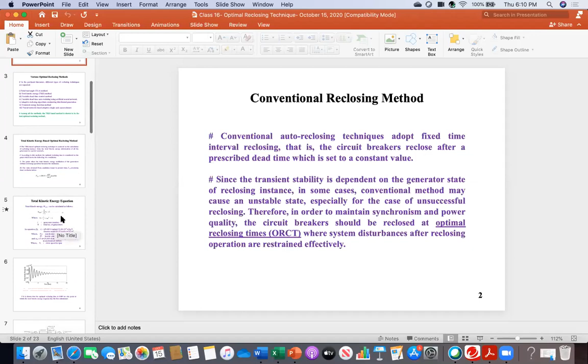Sir, these auto reclosing breakers are mostly used in the distribution systems, right? Yes. So now, because it depends on country to country, these techniques vary. Some countries use conventional reclosing, but with a method where their waiting time is less, for example, reclose after 30 cycles. They have decided that waiting just 30 cycles is fine, so they have fixed their time at 30 cycles, that is enough. But I have seen up to 1.6, up to 1.8 seconds waiting time in some power networks, which is too long. So that's why the optimal reclosing method is coming.